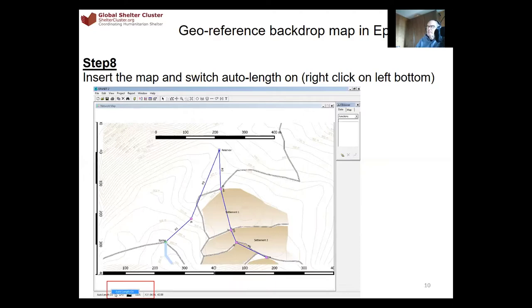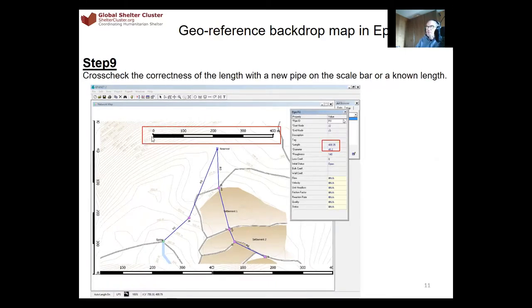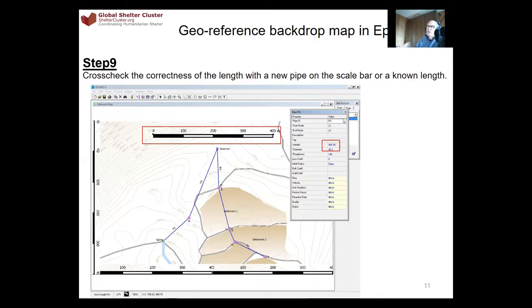Once the process is done, verify it was done correctly. Place two junctions — one at position zero and one at position 400 — then put a pipe between them and check the pipe's length in its properties. If the pipe is around 400 meters, your background map has been properly inserted. If not, there is a mistake somewhere. Once properly inserted, you just place junctions and pipe lengths will be estimated automatically. The rest is like workshops one and two: give elevation, water demand, pump curve, and pattern, then run the analysis.